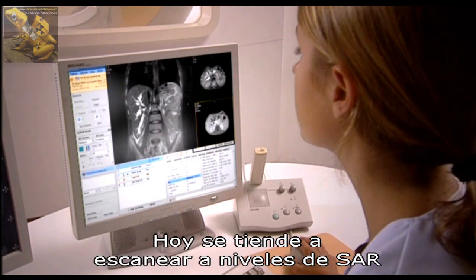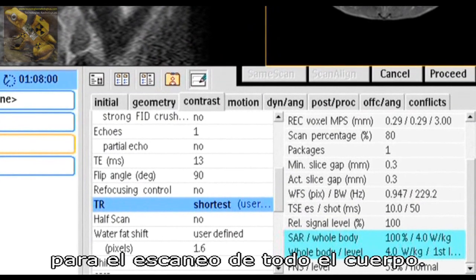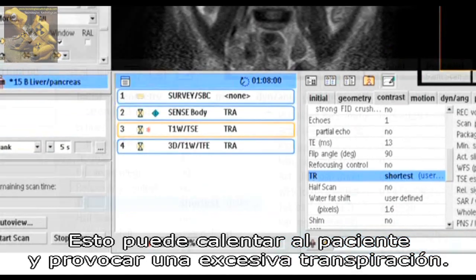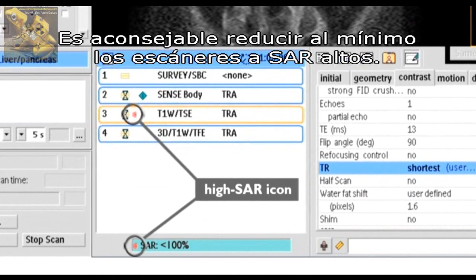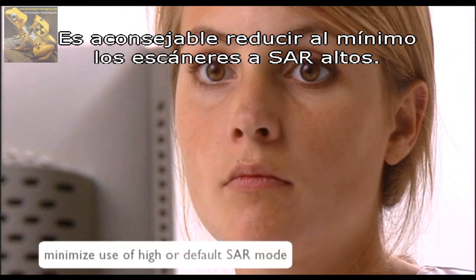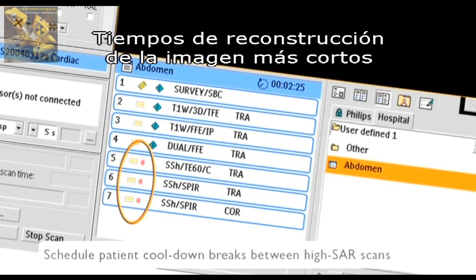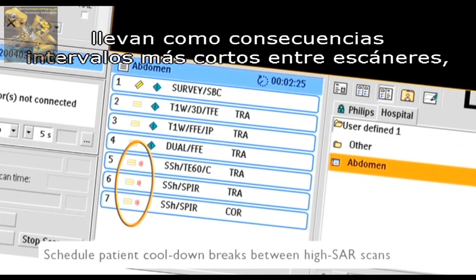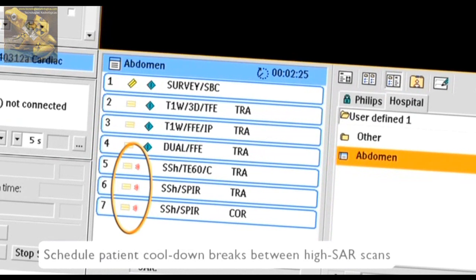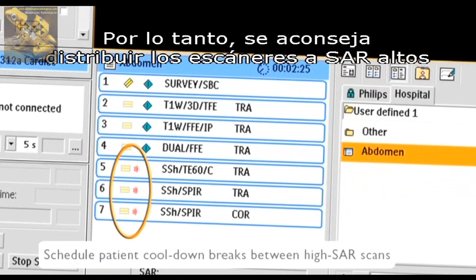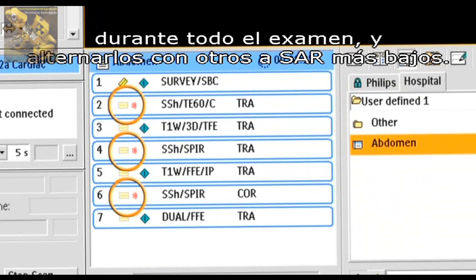There is a growing tendency to scan with SAR levels approaching the maximum of 4 watts per kilogram for a whole-body scan. This can warm up the patient, resulting in increased perspiration. It is advisable to minimize the use of scans with high SAR levels. Shorter image reconstruction times result in shorter intervals between scans, so the patient has less chance to cool down. It is therefore advisable to spread high-SAR scans across the entire exam by interleaving them with lower SAR scans.